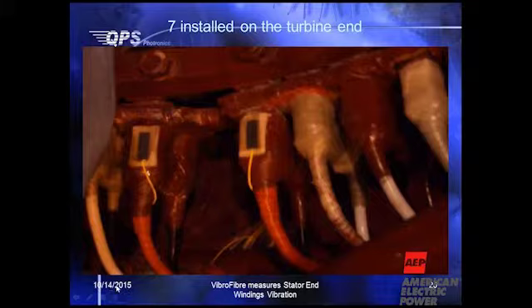So, a little slide to show you how we managed to install the sensor at the end winding. I mentioned before that this is cylindrical in structure, whereas our sensors are rectilinear. So how do we make it couple? Basically, we use silicon cloth, fiberglass cloth, and then soak it in resin and use a clamp to put it together.